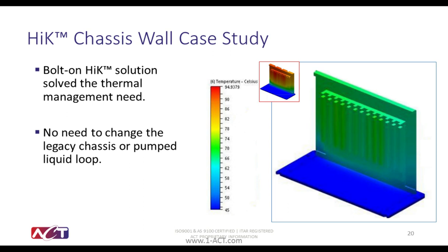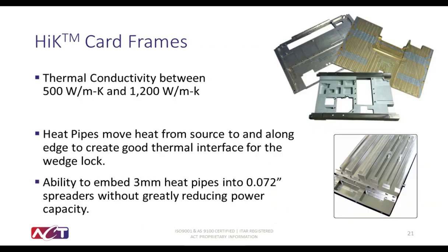And finally, we talked about frames, we talked about chassis walls, and we talked about heat sinks. Now we'd like to talk about the cards themselves that are put into these chassis. ACT has also worked on these card frames to turn them into HiK type solutions. By embedding heat pipes into the cards themselves, the components that are on those cards are directly in contact with the heat pipe, and the heat pipe transfers that heat out to the edges, where it then can be integrated into the chassis and rejected from the system by air or liquid. This is, again, a passive solution because the alternative here would be to potentially put fans within the chassis itself and/or pump liquid directly into the chassis, which again provides more complicated assembly as well as adds leak points that will decrease the mean time before failure.